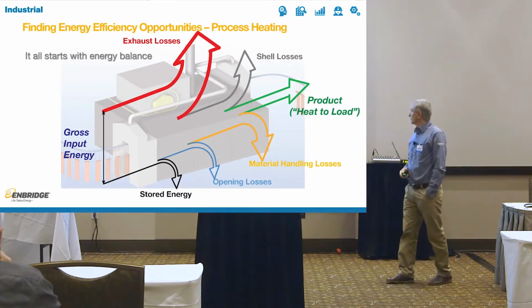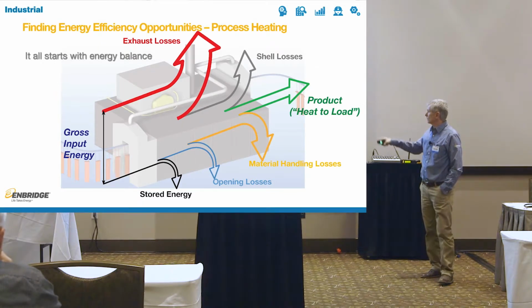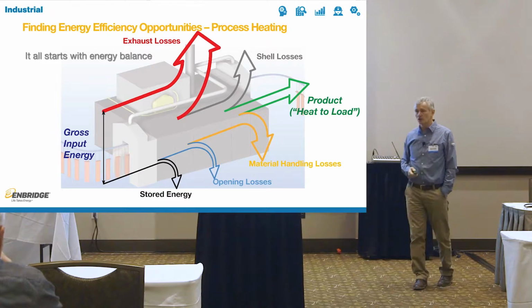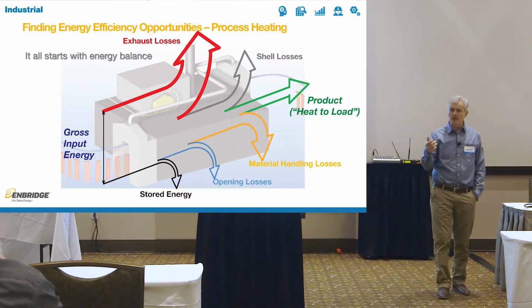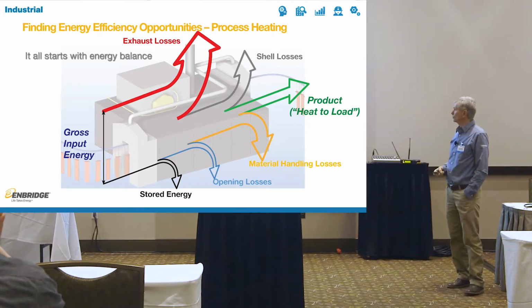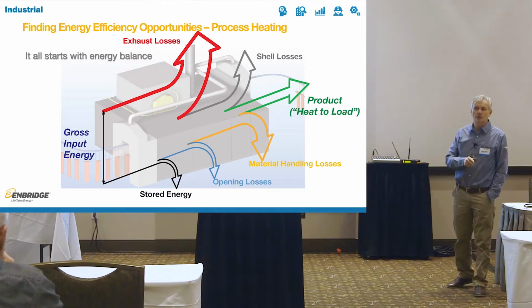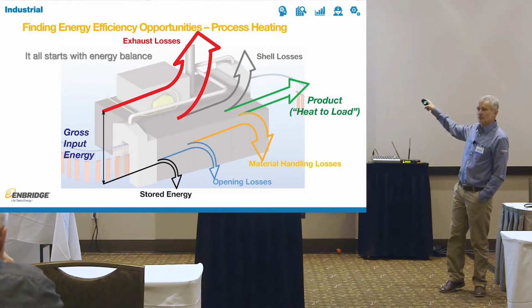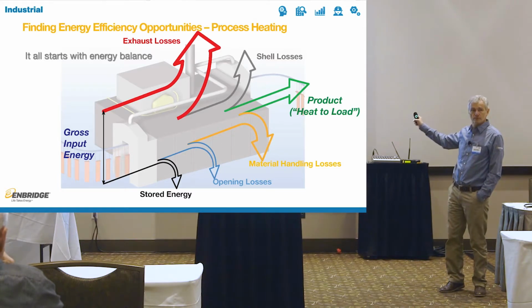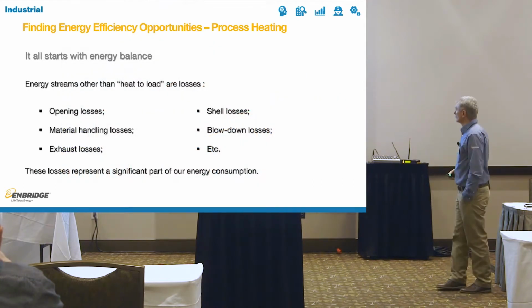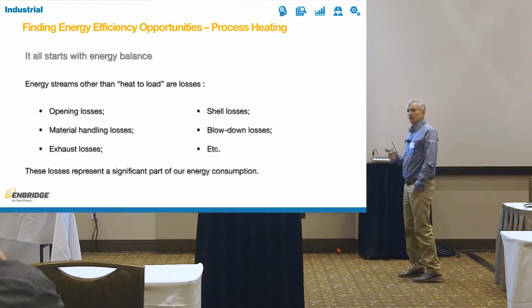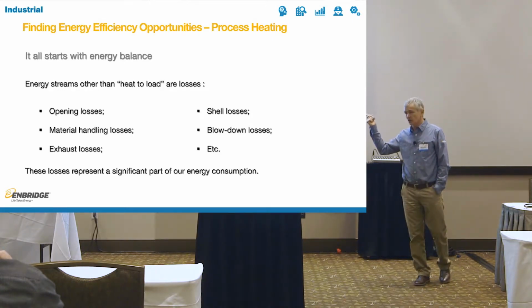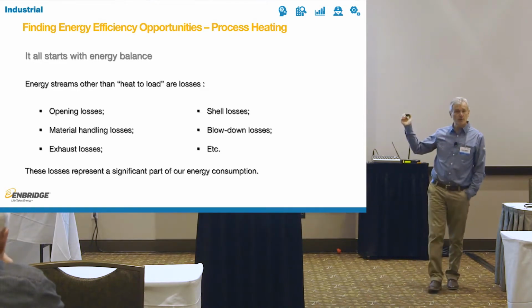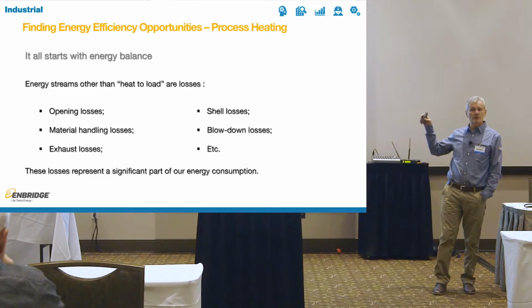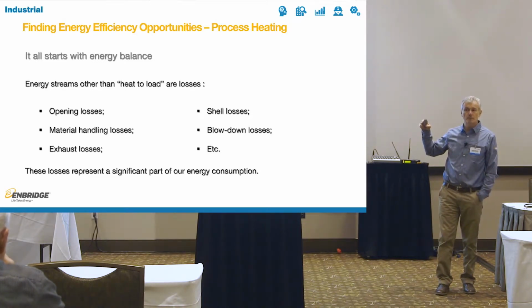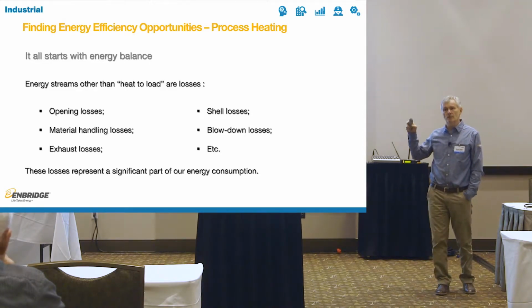So how do we know that? Well, you have heat to load, and then you have all these other losses: stored energy, opening losses, material handling losses, shell losses, exhaust losses. You have to do the energy balance rather than the air balance now to find out how much of all that combined turns into your gross input energy. All of those arrows are some sort of loss except for the green one. That's the one that you need. Anything that's not heat to load is a loss: opening losses, material handling losses, exhaust losses, shell losses, blowdown losses on the boilers, for example. All of those losses represent a significant part of your energy. You paid for them, you didn't use them at all. You're paying for something you're throwing away.